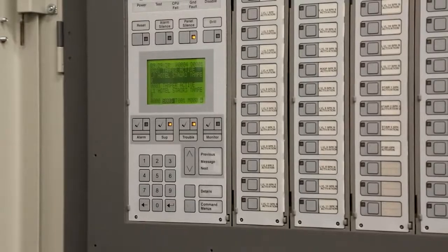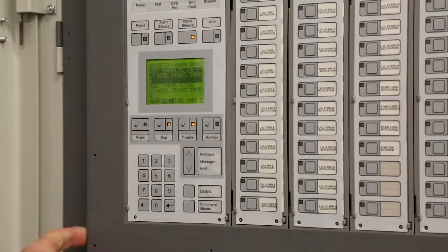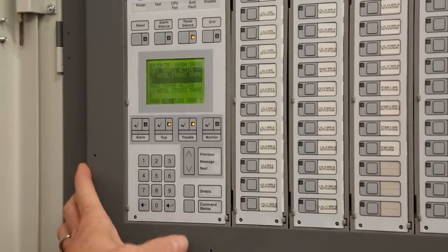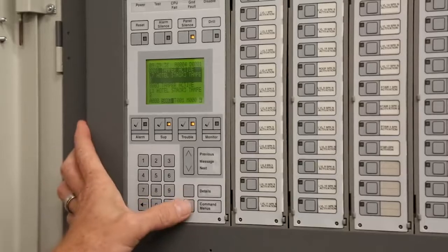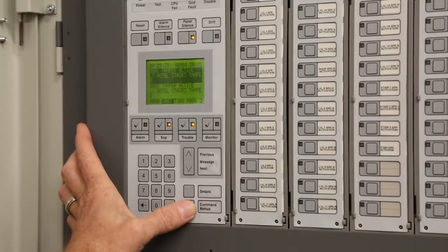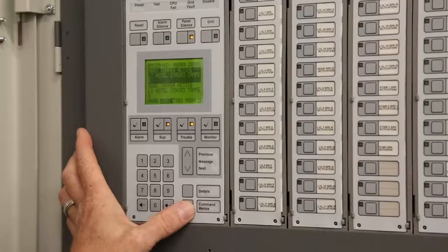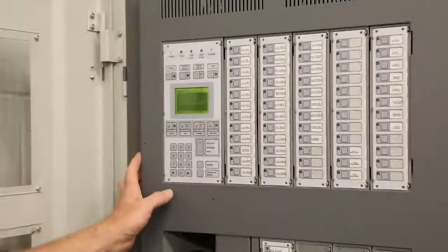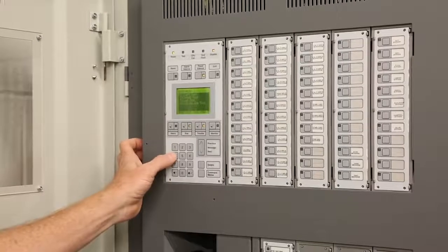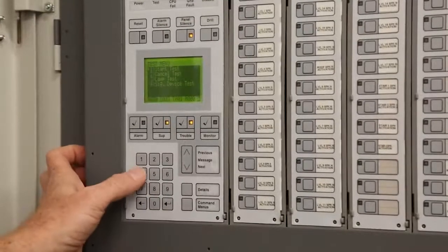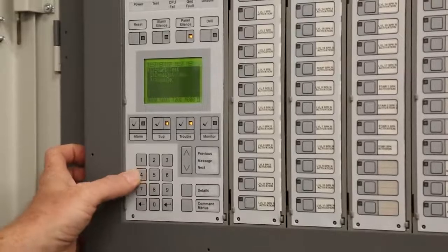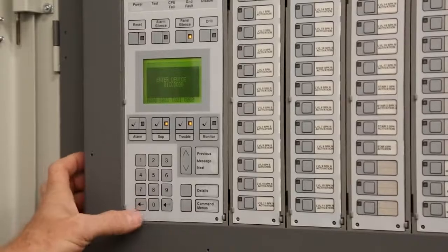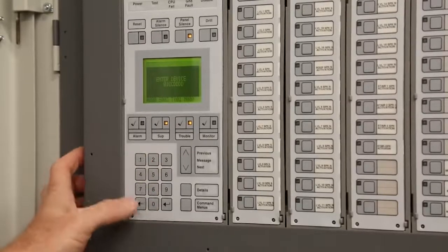Any questions? No? Okay, I guess now we could just simulate alarm coming in. I'll do the one out in the hallway. And again, I'm just simulating if smoke went in it, I'm just kicking it off by the panel. I can actually test it by this. And this part, it's number 8, number 4 is signal test, and then, like I said, I don't think you'll have to get into it. I'm just doing this instead of spraying the smoke detector.